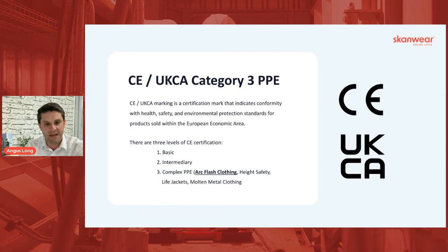An arc flash itself, I've already mentioned, reaches 19,000 degrees centigrade. To put the heat into perspective, hold your index finger 1 centimeter above a naked flame for 1 second - that's effectively 1 cal per centimeter squared of burn. That particular arc flash was a 14 cal arc flash, but it really shows you the intensity and heat that results from an arc flash.